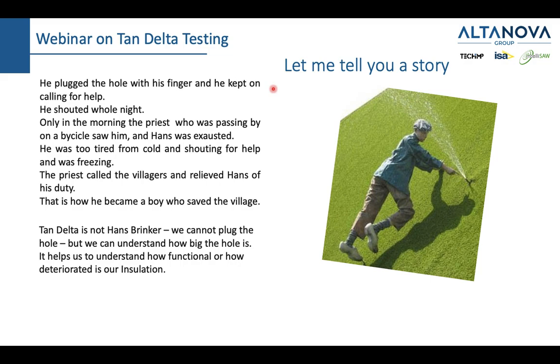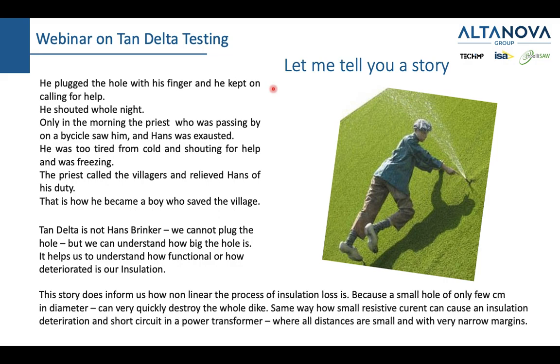We cannot, unfortunately, plug the hole. But what we can do with Tan delta is understand how big the hole is, let's say metaphorically. It helps us to understand how functional or how deteriorated our insulation is. So the story does inform us about the non-linear process of insulation deterioration, because a small hole, only a few centimeters in diameter in a dike, can very quickly destroy the whole dike. The same way a small resistive current can cause insulation deterioration and a short circuit in a power transformer. Because we all know that in a power transformer, all distances are very small and have even smaller margins.